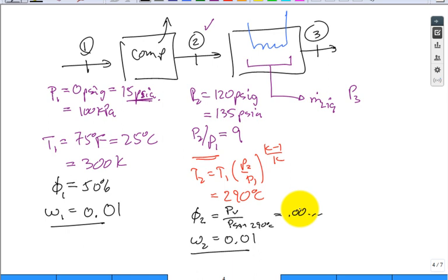And I've even heard stories, I'm not seeing it particularly in my own experience, where systems were run like that for multiple months, if not years, thinking that that was dehumidifying it. Oh yeah, the relative humidity went down, but what about omega? It didn't dehumidify anything. It was the same.